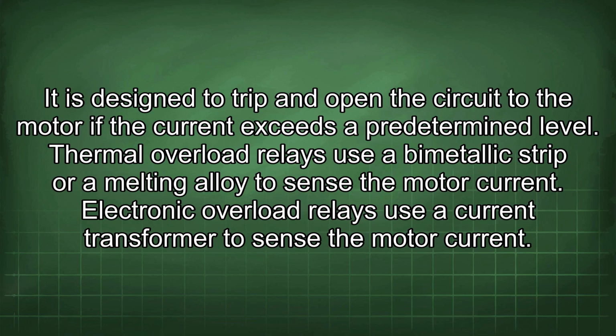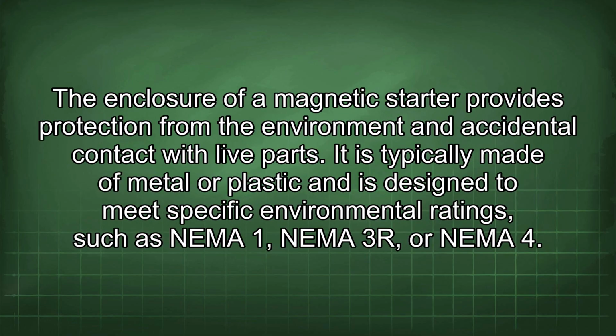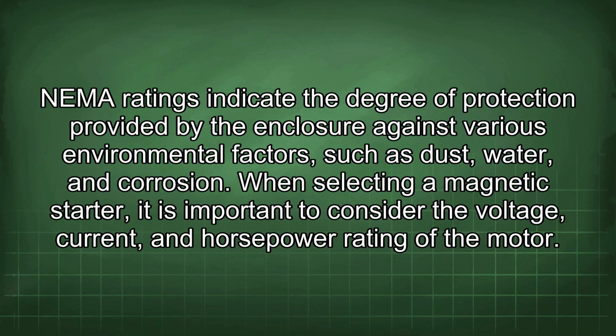Electronic overload relays use a current transformer to sense the motor current. The enclosure of a magnetic starter provides protection from the environment and accidental contact with live parts. It is typically made of metal or plastic and is designed to meet specific environmental ratings such as NEMA 1, NEMA 3R, or NEMA 4.